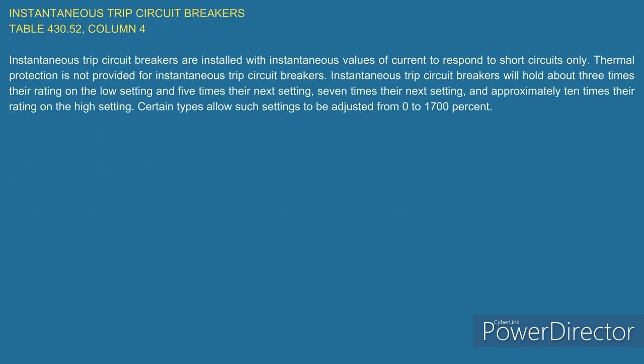Watch this. Now we're going to look at instantaneous trip circuit breakers. Now I'm going to read the second sentence here. It says thermal protection is not provided for instantaneous trip circuit breakers. Instantaneous trip circuit breakers, and pay attention to everything I'm telling you here, will hold about 3 times their rating on the low setting, 5 times on their next setting, 7 times on their next setting, and approximately 10 times their rating on the high setting.